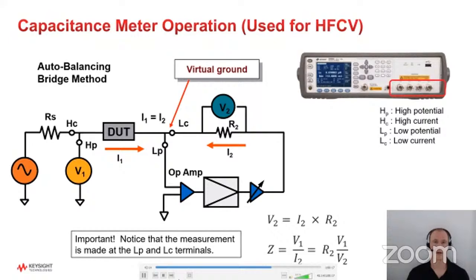So this diagram on this slide shows the operation of a capacitance, or really a generic LCR meter. Notice that the high current, high potential terminals feed into the DUT, but the actual measurement is made at the low terminals, the LC and LP terminals. So that's an important thing to remember, and I'll show why later. Also note that the simplified circuit, and it's pretty true, is similar to an op-amp circuit with feedback. So the terminals on the other side of the DUT actually are a virtual ground.